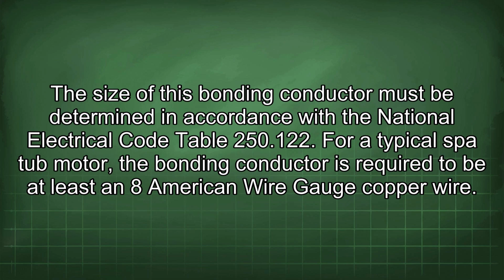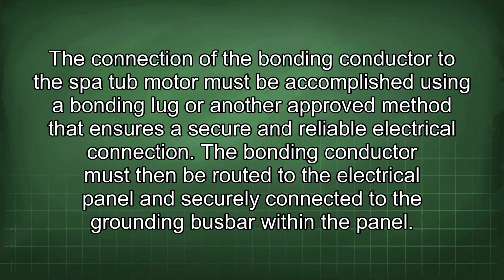250.122. For a typical spa tub motor, the bonding conductor is required to be at least an 8 American wire gauge copper wire. The connection of the bonding conductor to the spa tub motor must be accomplished using a bonding lug or another approved method that ensures a secure and reliable electrical connection.